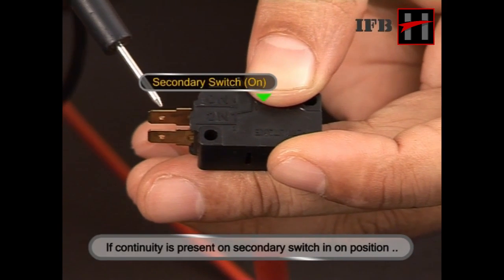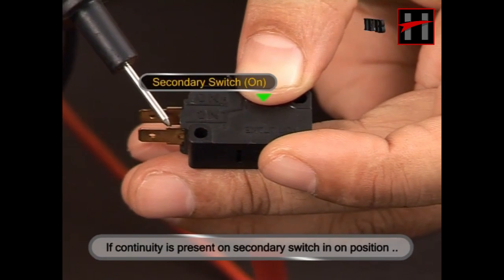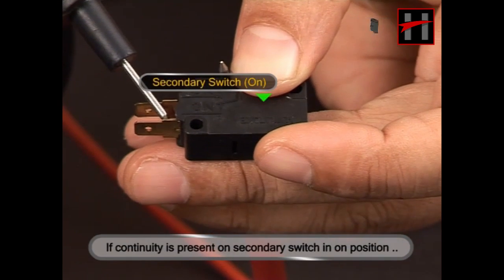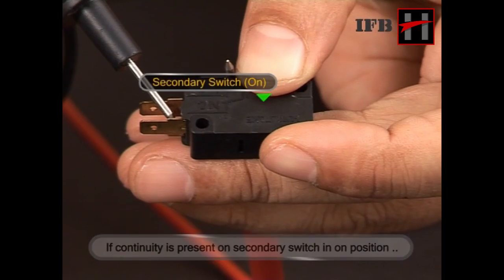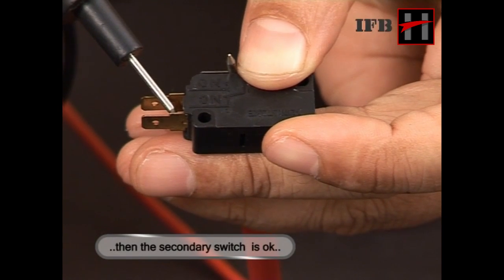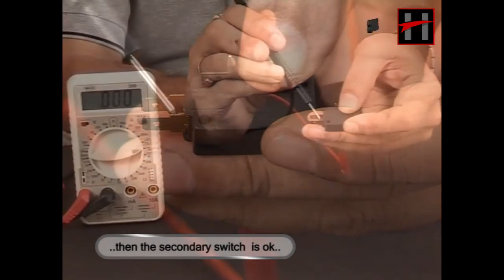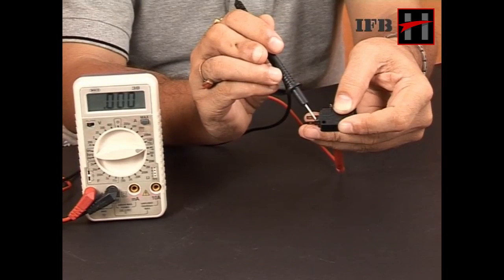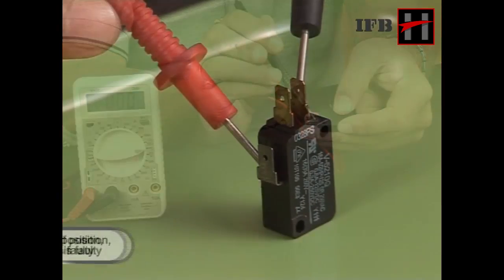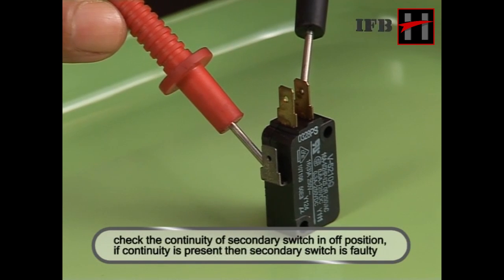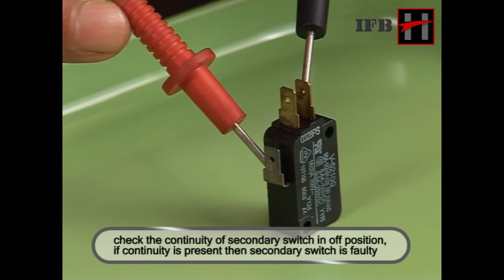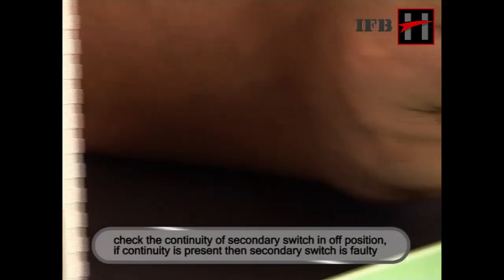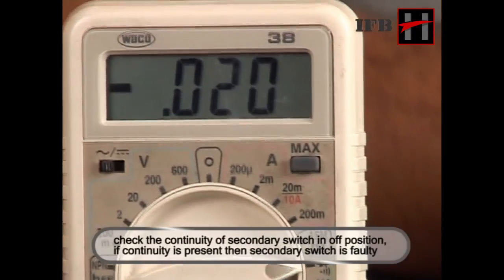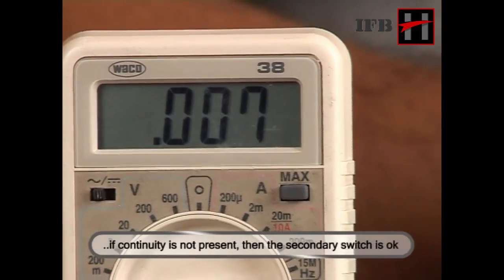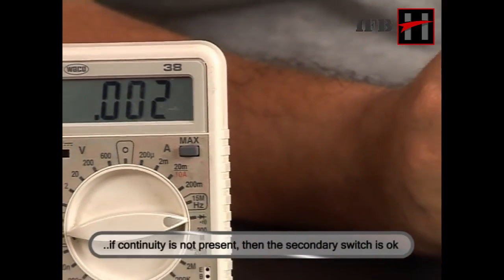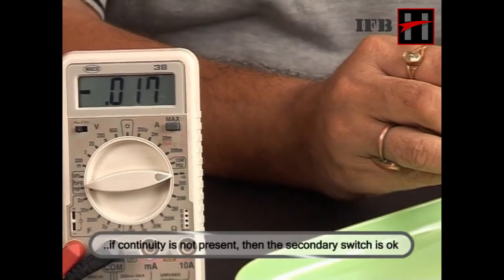If continuity is present on secondary switch in on position, then the secondary switch is OK. Check the continuity of secondary switch in off position. If continuity is present, then secondary switch is faulty. If continuity is not present, then secondary switch is OK.